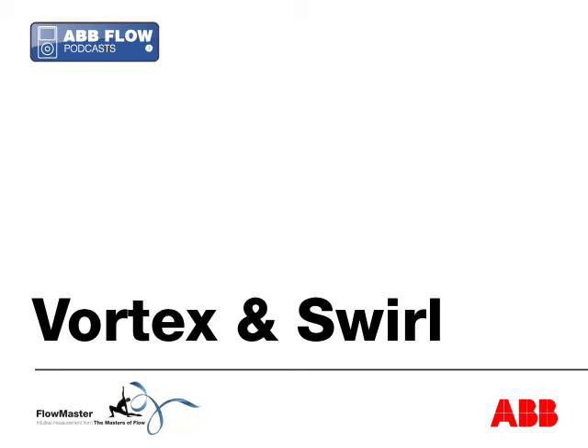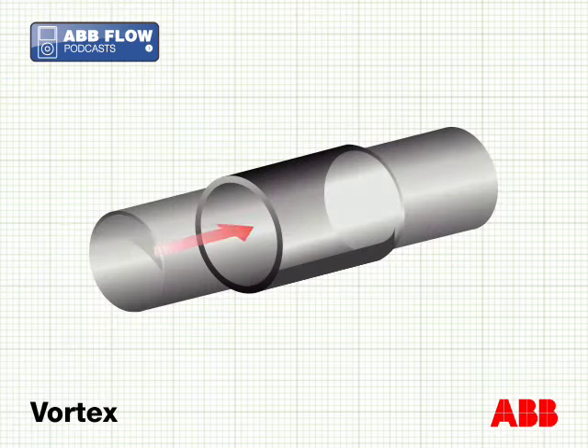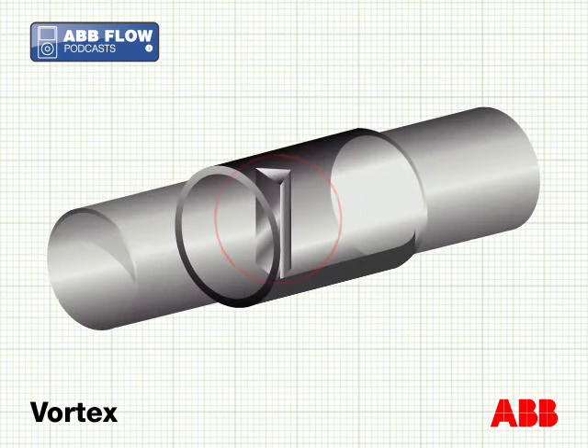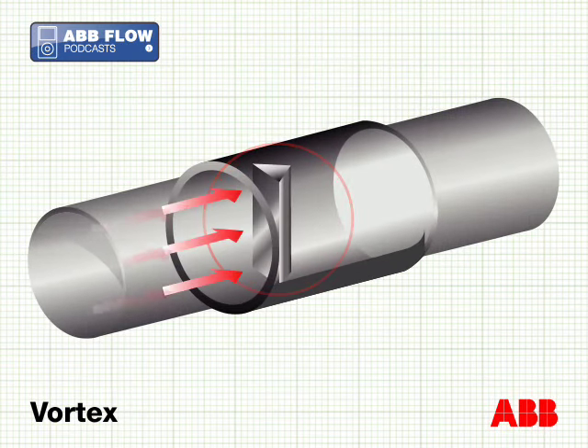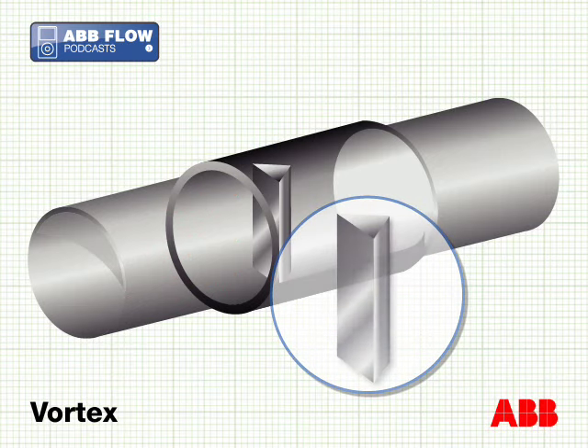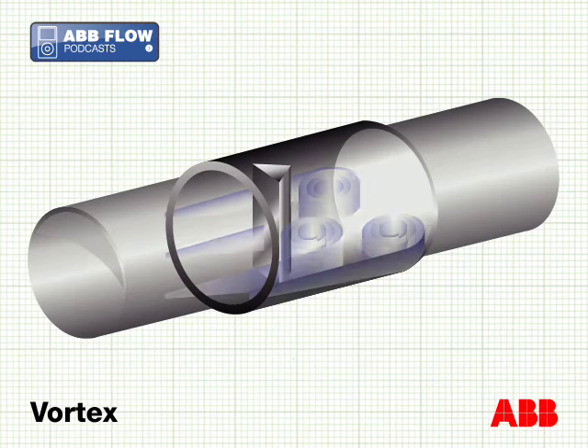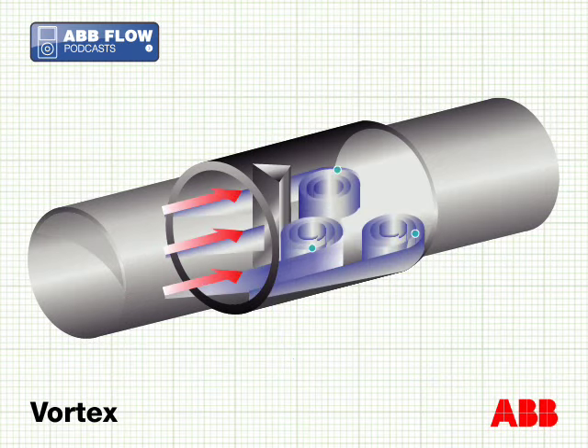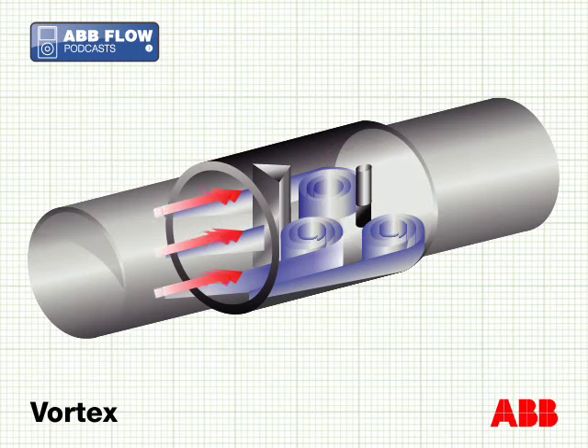The ABB vortex flow meter is based on the pressure variations which occur when a flow is interrupted by an obstruction. Here the flow passes a wedge-shaped obstruction called a bluff body, inducing eddies or vortices in the flow. These vortices occur at a rate proportional to the velocity at which the fluid is moving. A sensor detects the pressure variations caused by the vortex stream and transmits the signal to the electronic signal conditioner.